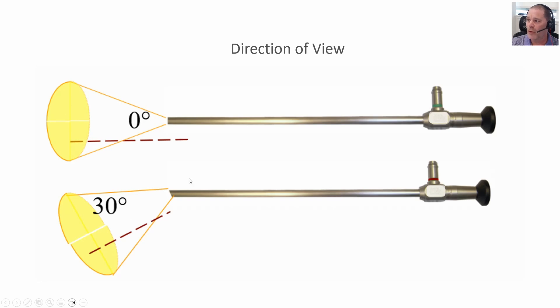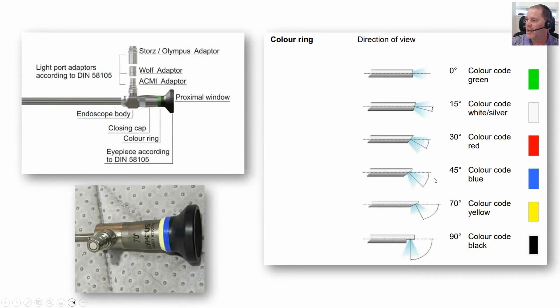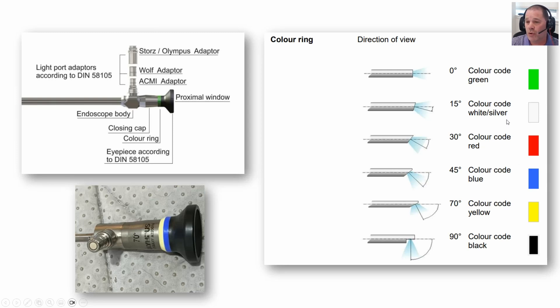Looking at this particular chart, we also have 45, 70, and 90 degrees. The color coding sequence here is not a universal standard — this is important — so different manufacturers may use different colors. A green for a Smith & Nephew telescope might mean something different for an Olympus telescope. So we don't want to assume when you put it in a set in prep and pack that this is zero degree or a 30.